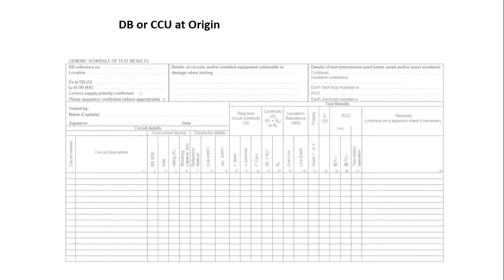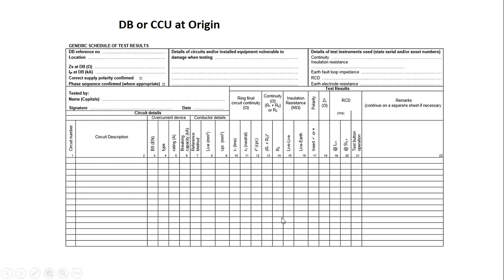On the schedule of test results for the distribution board or consumer unit at the origin, the top left-hand box where you can see ZS at dB — that's where we now write that value. In this example, it was exactly the same as the ZE. However, we still write it on even if it's the same. In a domestic environment, it can often be the same, or with parallel paths connected it could be slightly lower. You just do the test as shown and write the value in this box on the schedule of test results.